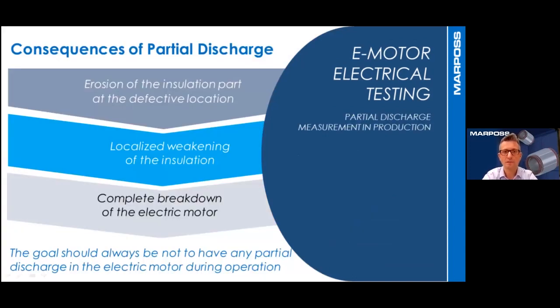The consequence of permanent partial discharge is a slow but continuous weakening of the functional parts of the insulation. A continuous erosion of the insulation at the defective location. This inevitably causes a localized weakening of the insulation, which will soon not be able to resist the stress. And this leads to a complete breakdown and so to a failing of the electric motor. The goal should be to have no partial discharge in the electric motor during operation.